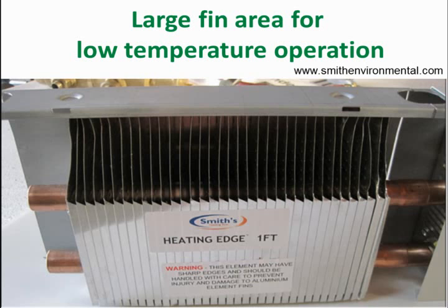Yet another product that I found when I was searching around to see what's out there is this product from Smiths. And what they've done is they've basically taken that same concept of a double-tiered or double-stacked element, and they put it into one product. Here they've got both tubes going through that fin as a one-piece fin. You can see they've got them real tight together. They've got a very deep fin. It's a very tall fin, 3/4 copper going through that.